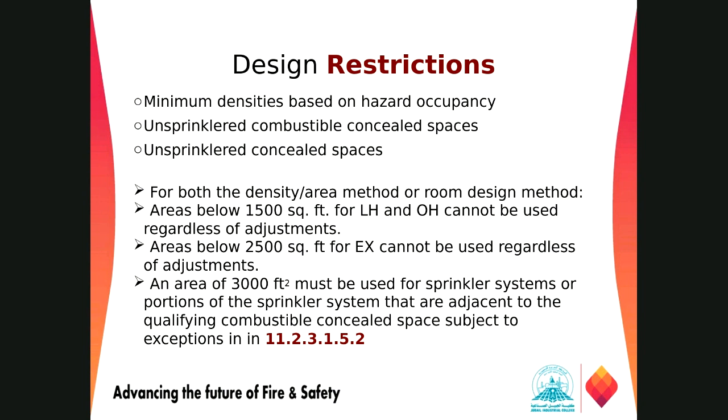We cannot go below 1500 square feet for light hazard or ordinary hazard regardless of adjustments. Areas below 2500 square feet for extra hazard cannot be used regardless of adjustment, and an area of 3000 square feet must be used for those areas regardless of adjustment.